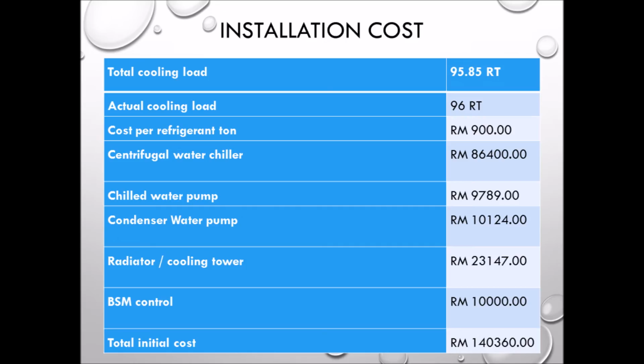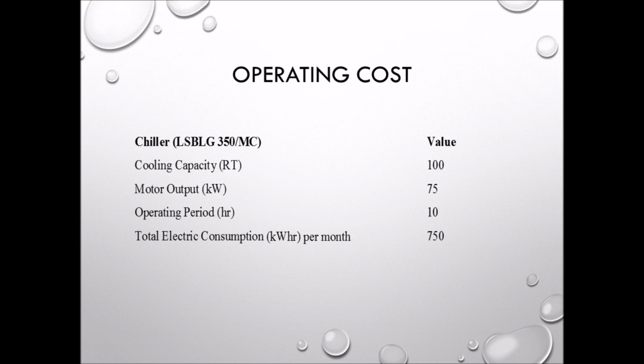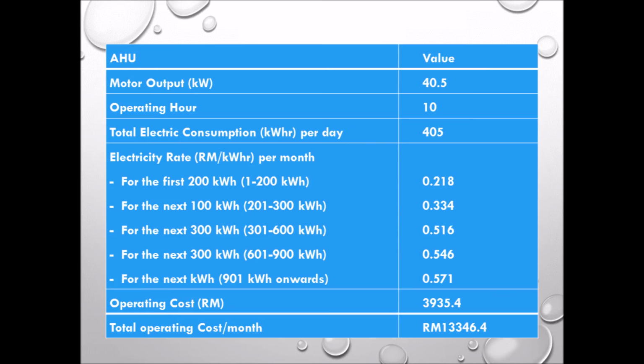So this is the installation cost, our initial cost for the office building. So the total initial cost is around 140,360 ringgit. For the operating cost of the chiller, we got the total electric consumption per day at around 750 kilowatt hour. And for the air handling unit, we got the total electric consumption per day at around 405 kilowatt hour. So the total operating cost for both the air handling unit and the chiller is around 13,346 ringgit per month.